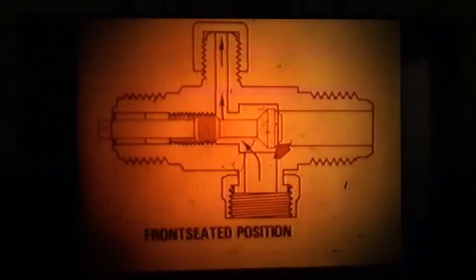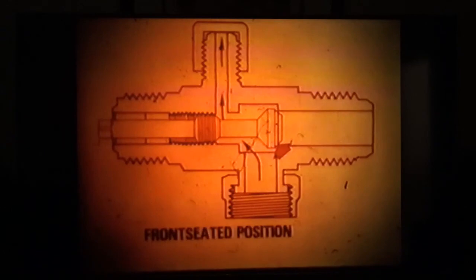Stop the engine, remove the service valve stem caps, and turn both service valve stems fully clockwise until they are front-seated. Loosen the cap on the discharge service valve port about 1/4 turn and allow the refrigerant vapor to escape until the compressor is relieved of pressure.